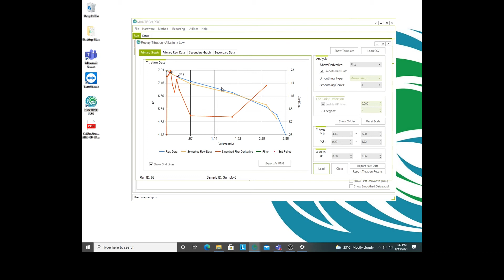So it's continuing with sampling of the next sample, but it's a very open software in the sense that it's not locking you from going and looking at previous data or anything like that. So I can right away just go here, review my titration data. We'll go ahead and load one of the more recent titration curves here. And right away, there you go. You can see it's got the derivative. So if you were using inflection points and inflection-based endpoints, it calculates that for you. Or if you're doing just the straight alkalinity curves, it just does it based off set endpoints. So it's nice and easy for you.